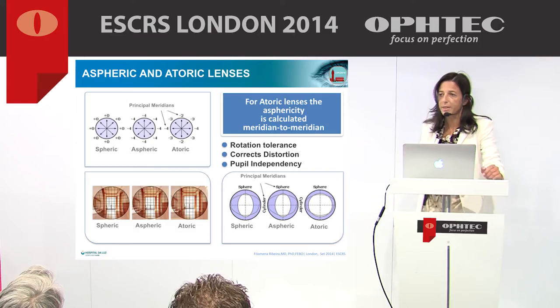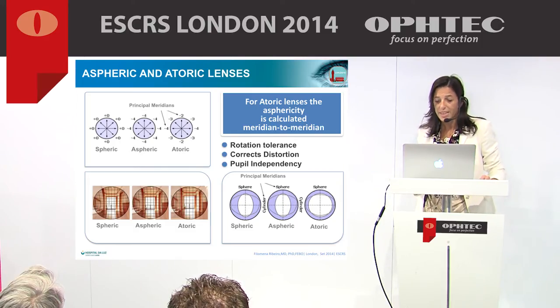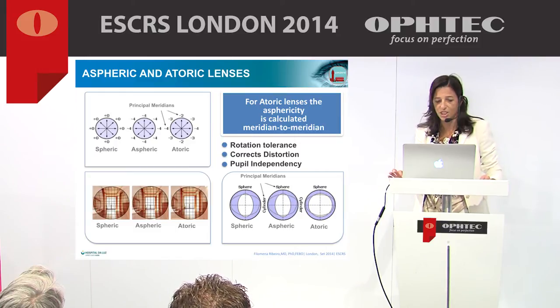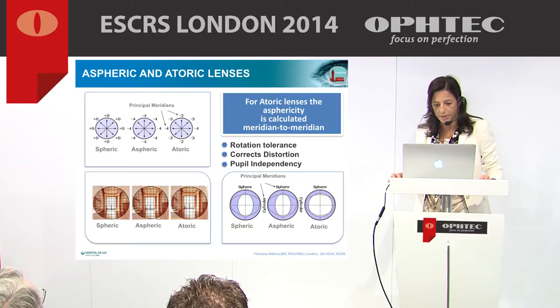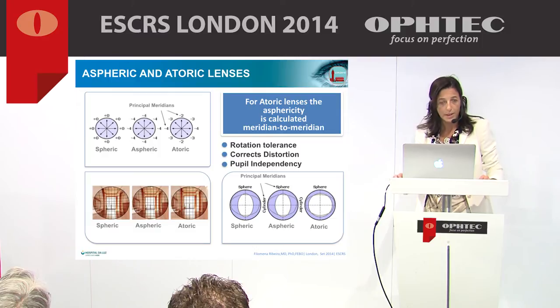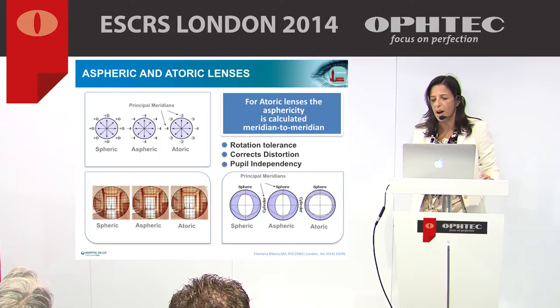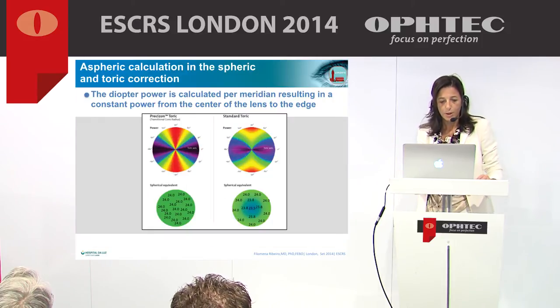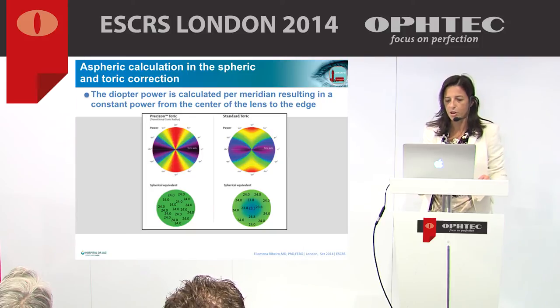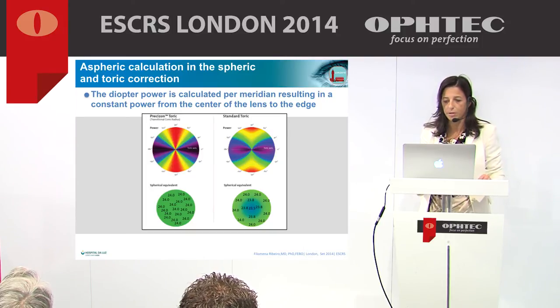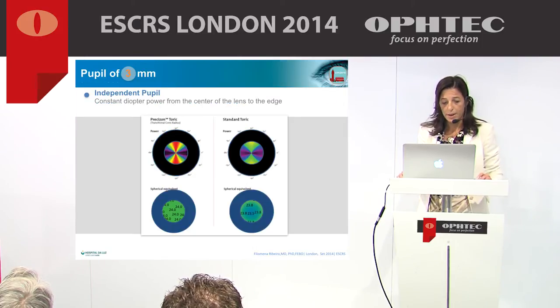In the atoric lens, note how the relative asphericity correction factor changes from meridian to meridian. Each meridian of the lens has been adjusted by changing the amount of asphericity from one meridian to another. The atoric lens can therefore provide a wider field of vision and optical performance superior to conventional lens designs over a wide range of lens powers. With this approach, the spherical equivalent diopter power will be constant from the center of the lens to the edge, which is especially important in larger pupil profiles.